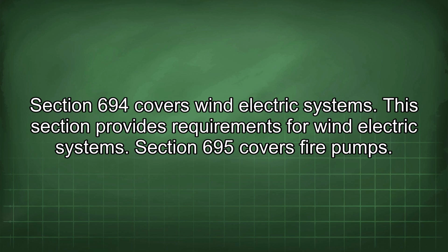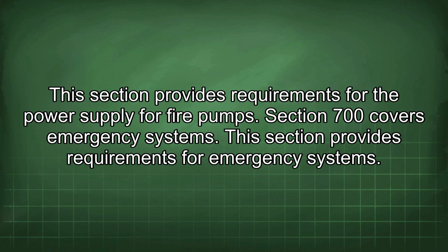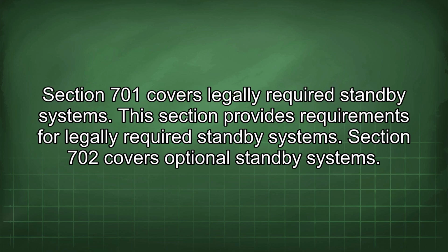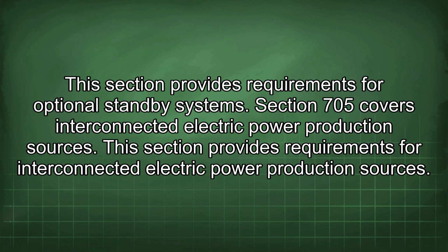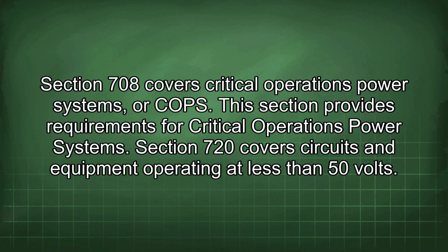Section 695 covers fire pumps. This section provides requirements for the power supply for fire pumps. Section 700 covers emergency systems. This section provides requirements for emergency systems. Section 701 covers legally required standby systems. This section provides requirements for legally required standby systems. Section 702 covers optional standby systems. This section provides requirements for optional standby systems. Section 705 covers interconnected electric power production sources. This section provides requirements for interconnected electric power production sources. Section 708 covers critical operations power systems, or COPS. This section provides requirements for critical operations power systems.